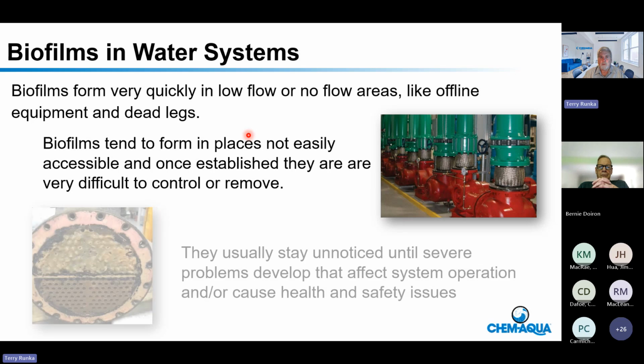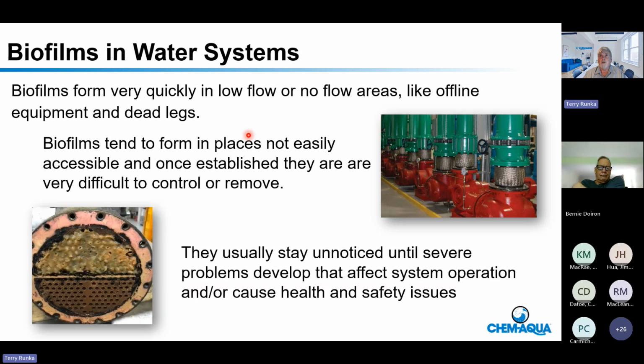So where do biofilms come from? Well, biofilms form very, very quickly, in minutes actually, in dead leg and low flow areas of your system. But our system runs 24/7 when it's hot. And I'll be standing there right next to a pump. Oh, well, that pump's not running. Oh, well, that's redundant in case this one breaks. So that pump and that entire line is full of stagnant water where biofilms are growing. Standby chillers. Most places have an extra chiller, or it comes on when it's 80 degrees.